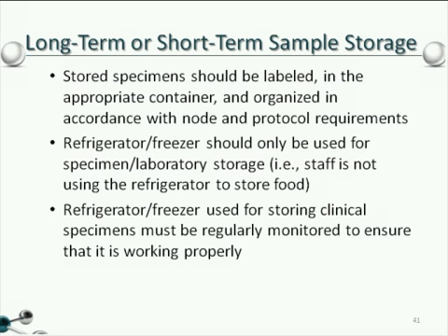And if something should happen with a -80, they will alert whoever's on the contact list that, hey, you need to get here, your -80 has gone down. You should have a loaner freezer on hand to remove those samples and store them so that there's no jeopardizing of the sample, because they're precious. You get them that one time, and you want to make sure that they're viable. And also, on that note, make sure that contact person is accurate. It shouldn't be a study coordinator that left the lab 3 years ago or left the site 3 years ago. Keep that contact current.